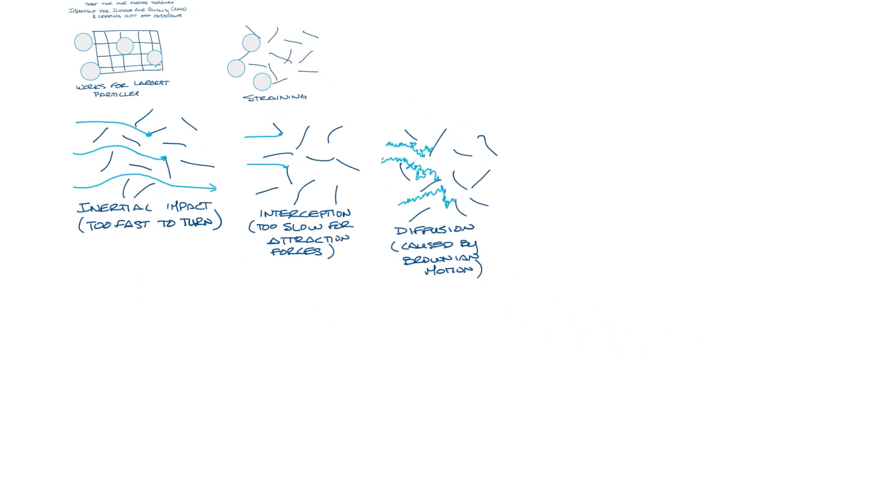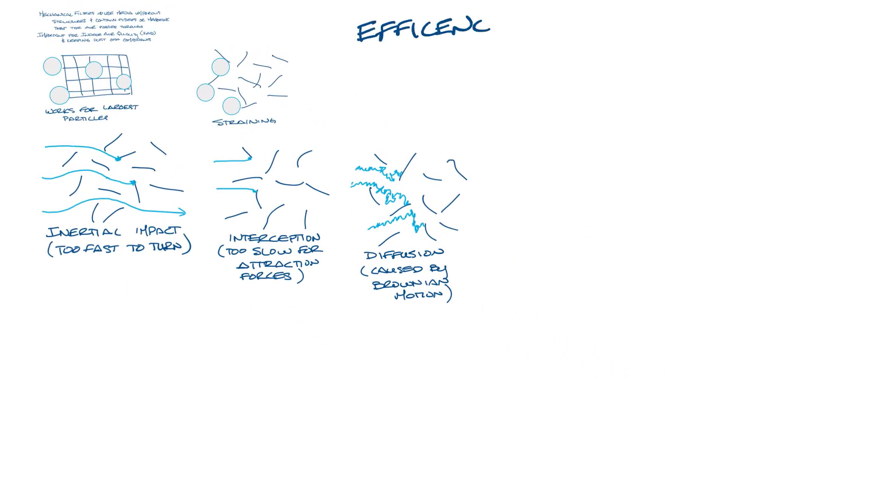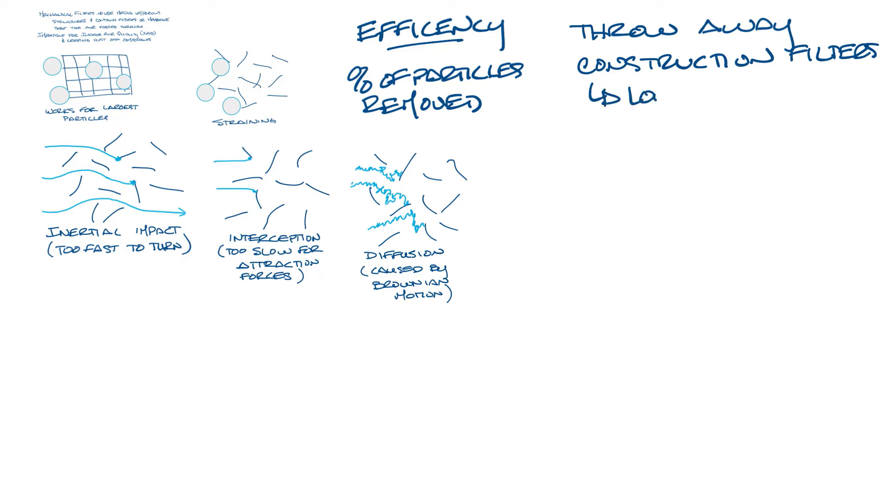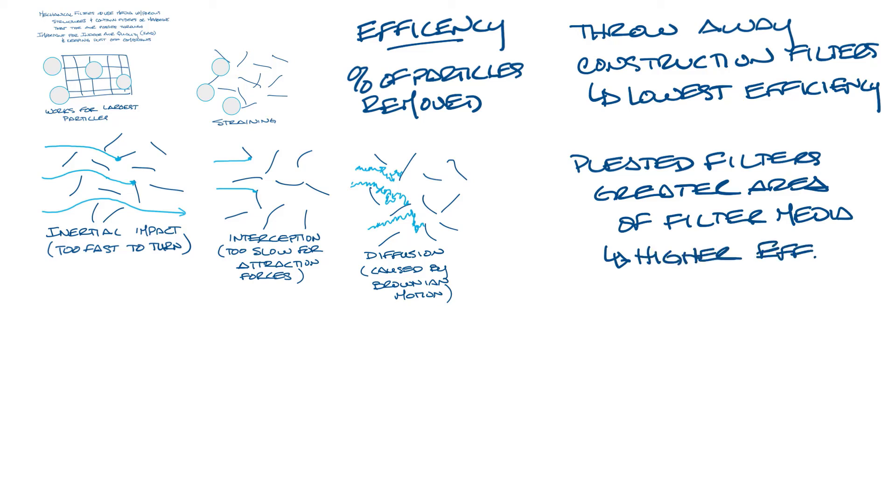The efficiency of a filter is basically the percent of particles removed from the airstream. Lower efficiency filters are usually throwaway filters. These are like the cheap fiberglass filters that are used during construction to keep construction dust out of the equipment. Pleated filters would be the next step up in media. This gives a larger area of filter media than the fiberglass filters so they have higher efficiency. From here you get into deeper filters like bag pocket or V-bank filters which are usually about 12 inches deep and they have higher filter media area and a higher efficiency.